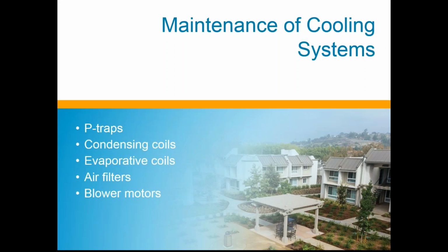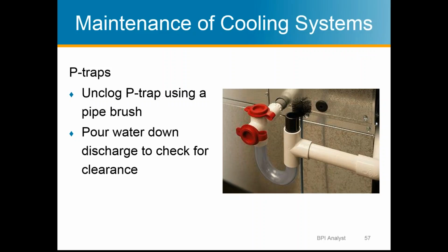A little bit on maintenance of the cooling systems. The big maintenance items are going to be P-traps, the condenser and evap coils, air filters, which we've already touched on, and the blower motors. And for the P-trap, there's a picture of the fanciest P-trap I've ever seen. But the P-trap is there. It's found near the evaporator coil, which is part of the air handler.